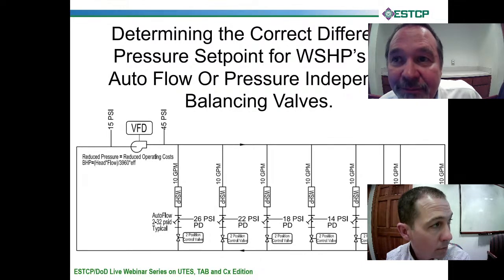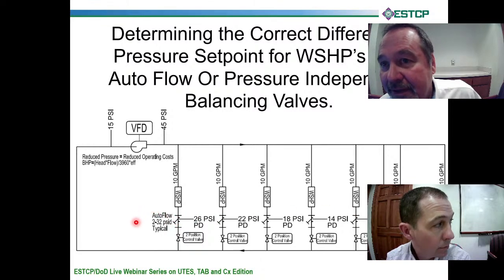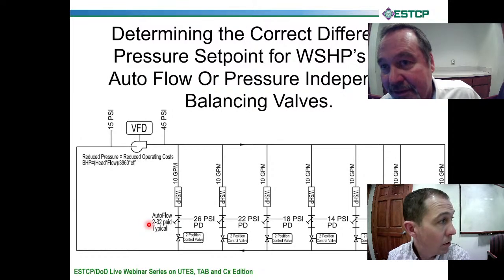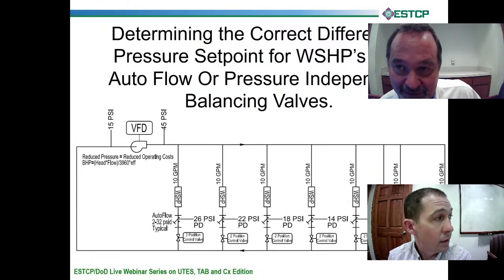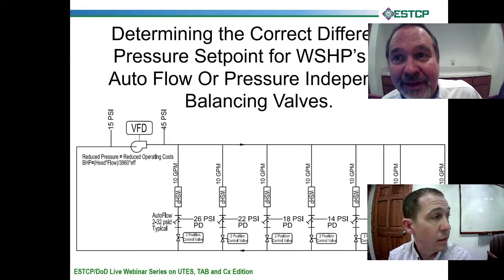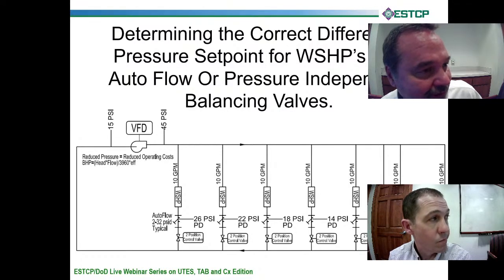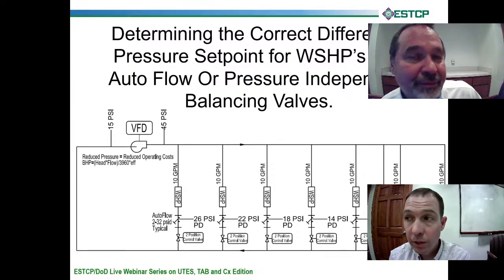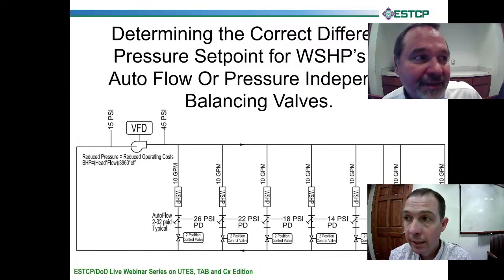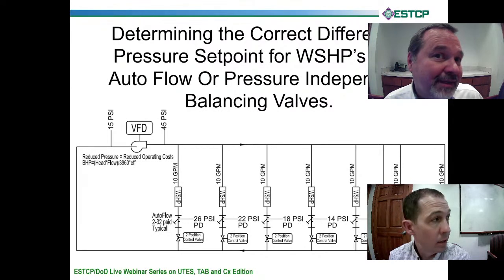So said another way, we've got to keep at least 2 pounds, somewhere between 2 pounds and 32 pounds, as Brandon indicates here. That's for that valve to truly control the flow at whatever design set point is. It needs a differential pressure between 2 and 32. But the differential pressure sensor, and sometimes there's multiple ones, but a rule of thumb is 2/3 of the way down the piping hydraulically. So the differential pressure here is going to be higher than 2 pounds. But what would you say, Brandon, the typical range we've encountered over the years, chill water, hot water? For the differential pressure sensor? Set point. Yeah, I'm going to just pick a number, 10. 10 PSI.